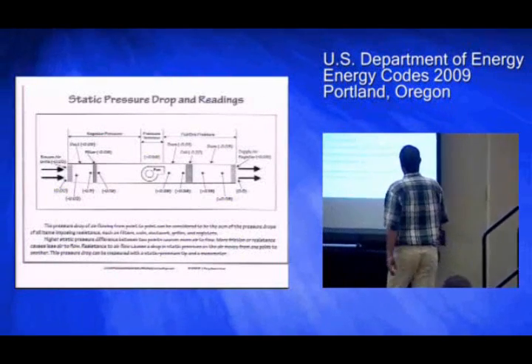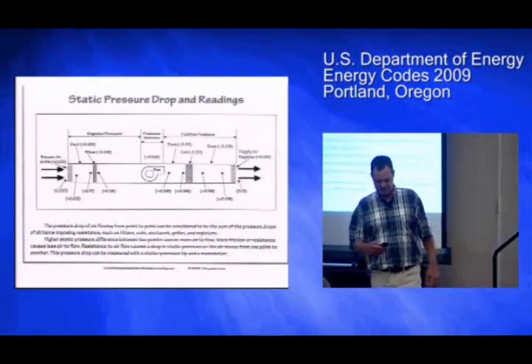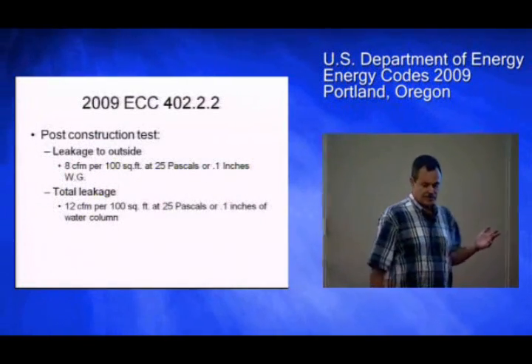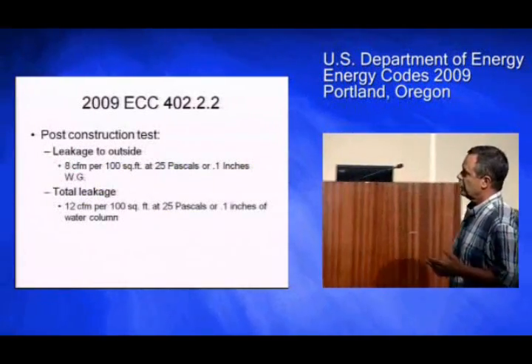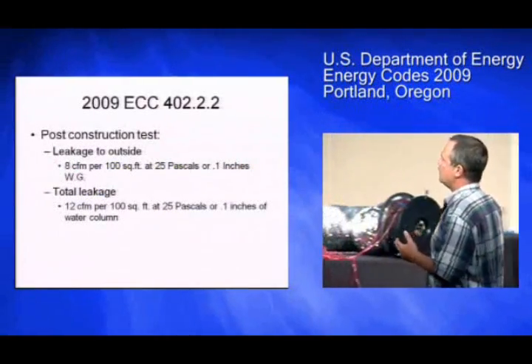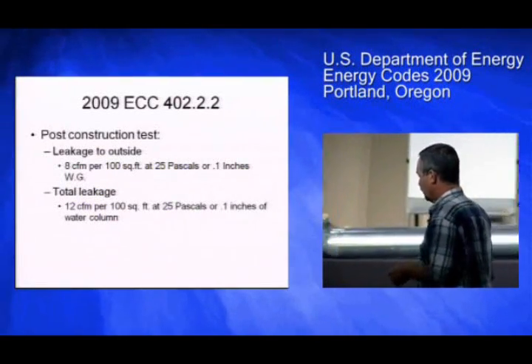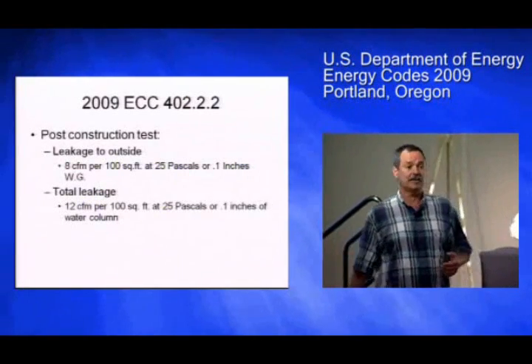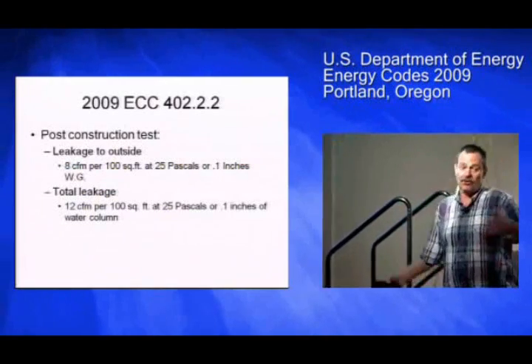What this chart says — in inches of water column — is the closer you are to the fan, the higher the pressure. There are two test options. One is the post-construction test and one is at rough-in. At post-construction, they are allowed up to 8 CFM per 100 square feet at 25 pascals or .1 inch water column. That's leakage to outside — the one with the blower door. Another way to express that is 8% of the floor area.